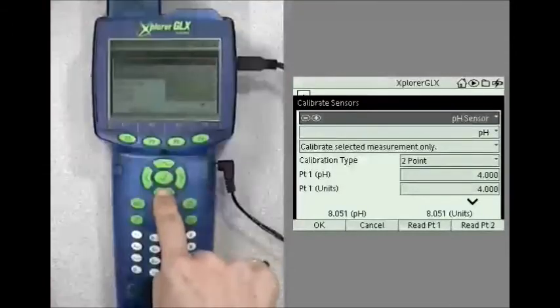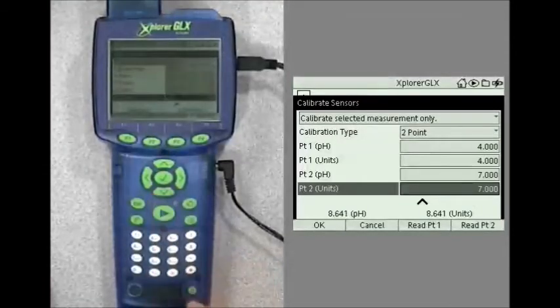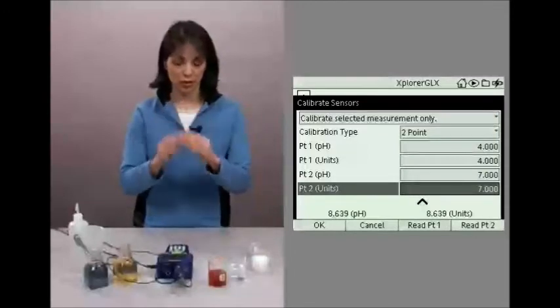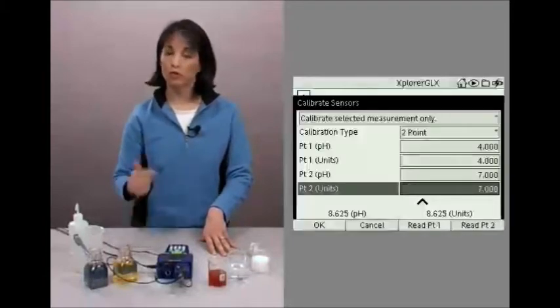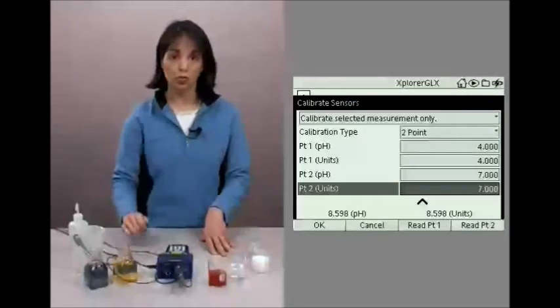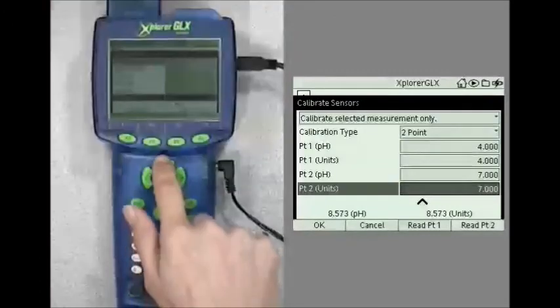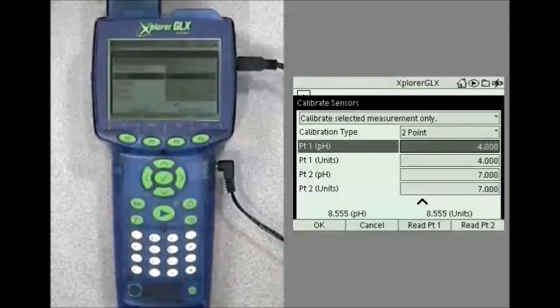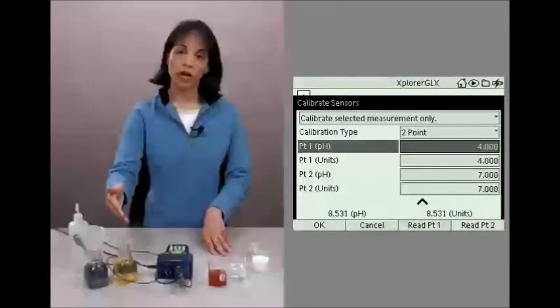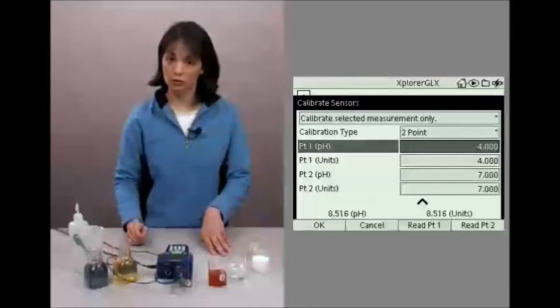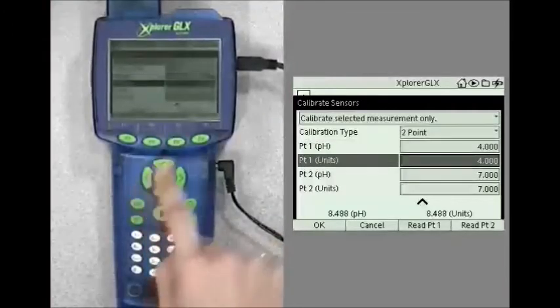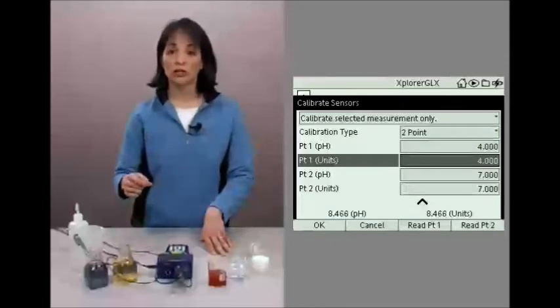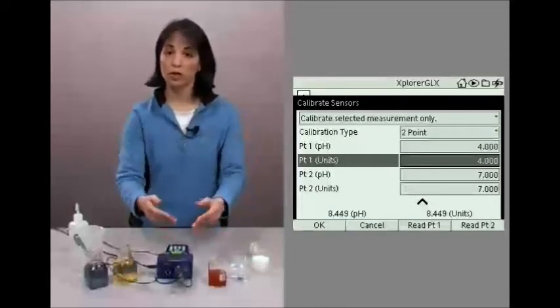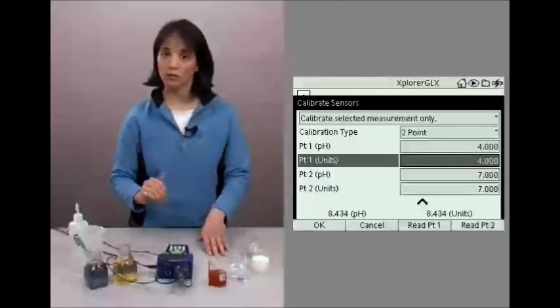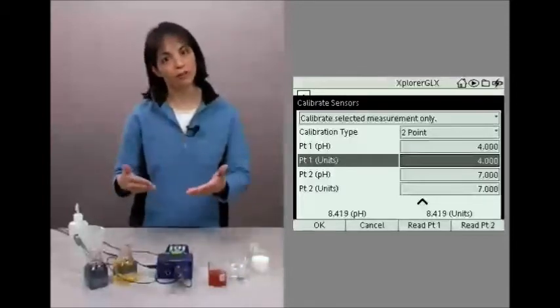First let's scroll down to the bottom of this calibration screen. And you know you're at the bottom because you see only that up arrow there. Take a look at the last 4 fields there. You see that there are 2 each related to each of the 2 points that we use for the calibration. In the first of those 2 fields, we tell the Xplorer GLX the value of the pH standard that we are using. In the second field, there, we tell the Xplorer GLX which raw value from the sensor it needs to associate with that standard. How do you know what raw value to stick there?